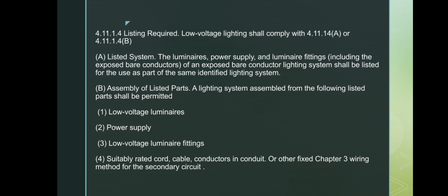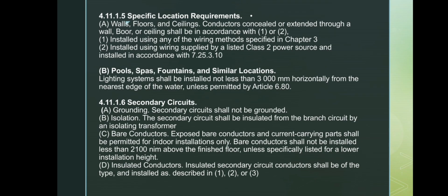Next is the listing required. All low-voltage lighting systems must be listed, meaning they are tested and certified for safety. There are two acceptable setups. First, a listed system where all parts, luminaires, power supply, and fittings are approved as one complete unit. Second, the assembly method, where we can combine listed parts such as low-voltage luminaires, the power supply, fittings, and properly rated conductors.